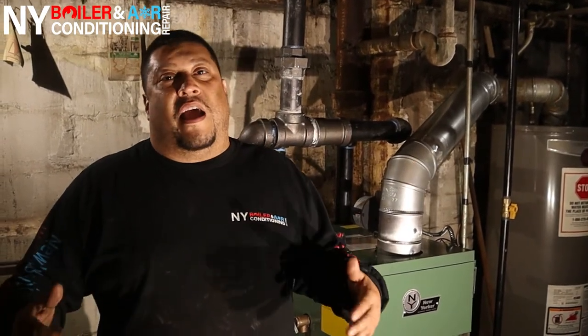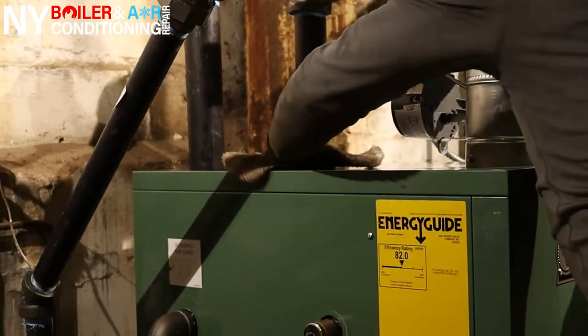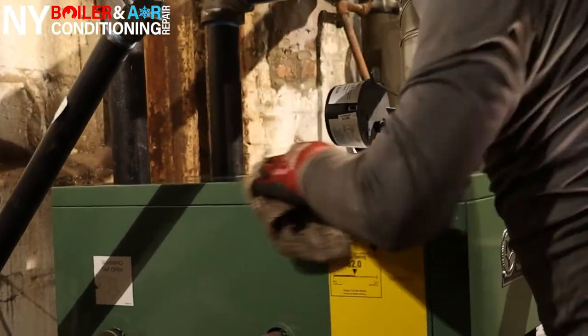We don't want that. Also, you might think you're low on water, and then all of a sudden you get a gush of water come back, and when it settles it'll flood the boiler. So you don't want any issues with flooding the boiler. These are things you want to check, not just the boiler — the boiler is just the heart of the system. Now we gotta check the tentacles, the arms and the legs.